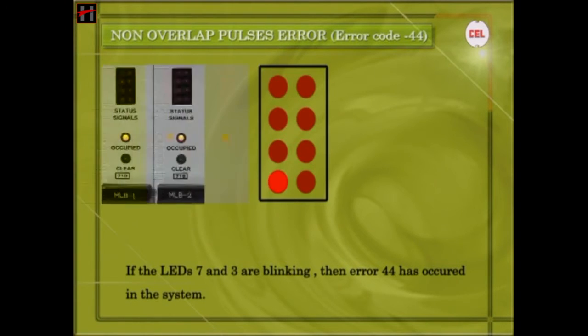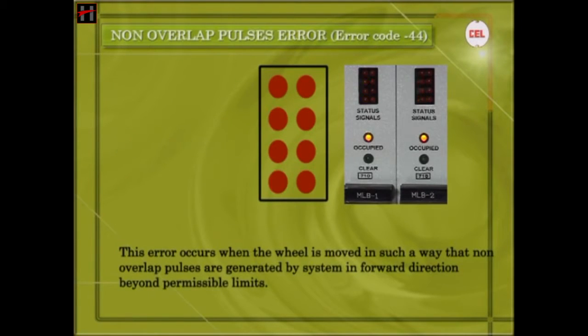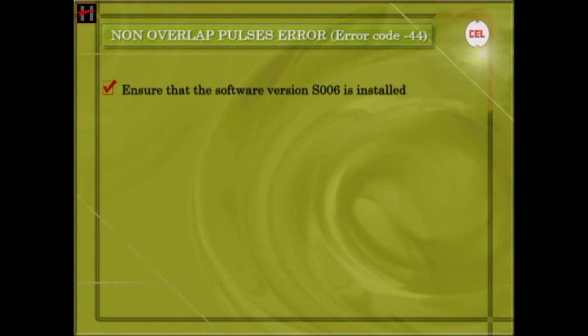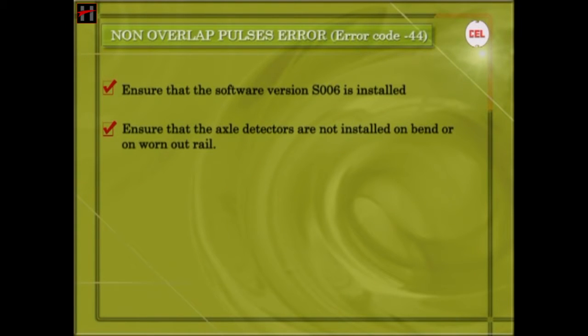If LEDs 7 and 3 are blinking, then Error 44 has occurred. This error occurs if the wheel is moved in such a way that non-overlap pulses are generated by the system in the forward direction beyond permissible limits. If the error is generated frequently, carry out the following checks: ensure that software version S006 is installed, and ensure that the axle detectors are not installed on curved lines or worn out rails.